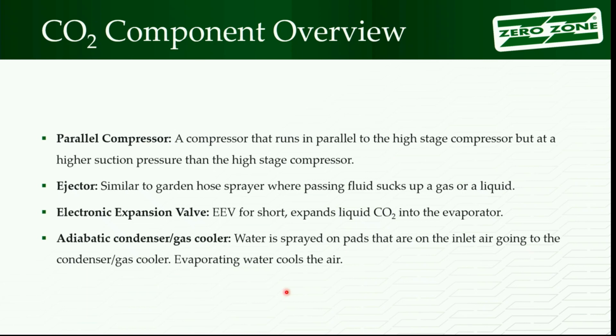When that happens, what the software does, it says, all right, we're getting to the point we don't want to be cycling our compressors. We're going to switch off, and we're just going to go back to the high-pressure expansion valve. So on transcritical days, with a lot of gas, you tend to see your parallel compressors running. It gets colder outside, less gas, you tend to see those dropping offline. You're just going through the flash gas. And it's all about cost. You want more compressors, smaller compressors? Yeah, we'll keep putting them on, but that cost goes up a little bit.